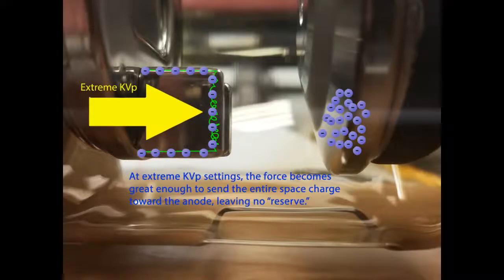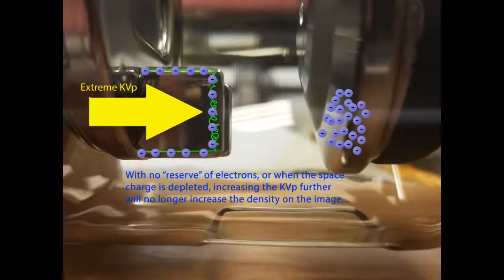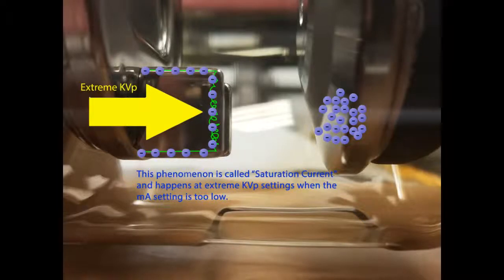At extreme KVP settings, the force becomes great enough to send the entire space charge toward the anode, leaving no reserve. With no reserve of electrons, or when the space charge is depleted, increasing the KVP further will no longer increase the density on the image. This phenomenon is called saturation current, and happens at extreme KVP settings when the mA setting is too low.